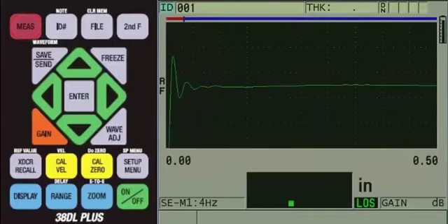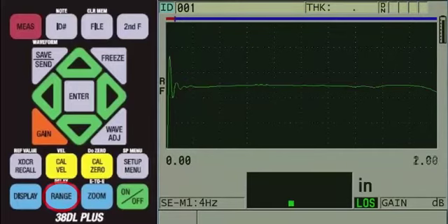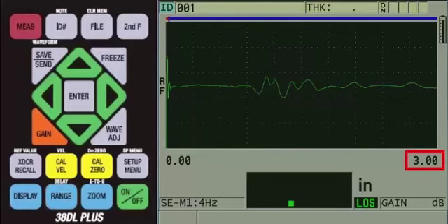Next, we will need to change our range. Currently, the range is set to 0.5 inch. If you are using metric units, it will be set to 10 millimeters. Given the thickness of our sample, we will not be able to see the back wall on screen since the range is currently set too low. To change the range, keep pressing the blue range key until the bottom right side of the screen displays 3.00. If you are using metric units, it will be set to 50.0.